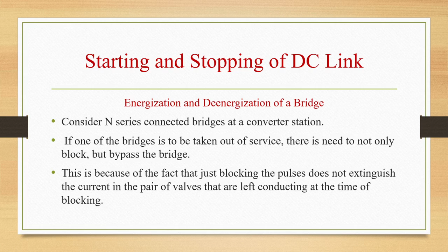The continued conduction of this pair will inject AC voltage into the link, which can give rise to current and voltage oscillations due to the lightly damped oscillatory circuit in the link, formed by the smoothing reactor and the line capacitance. The transformer feeding the bridge is also subjected to DC magnetization when DC current continues to flow through the secondary windings. The bypassing of the bridge can be done with the help of a separate bypass valve or by activating a bypass pair in the bridge, that is, two valves in the same arm of the bridge.